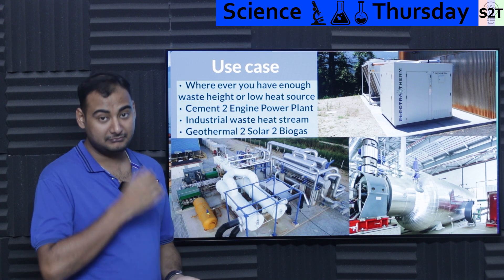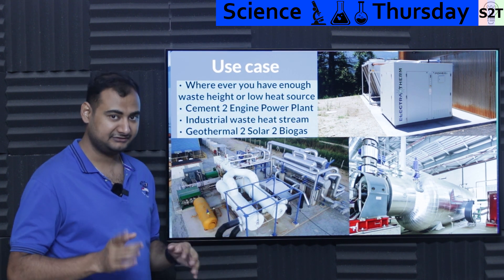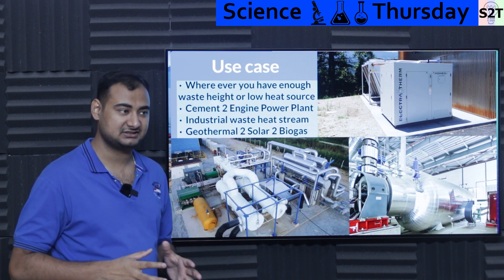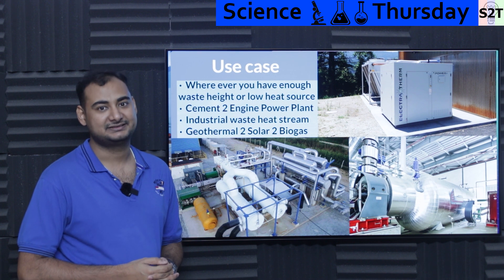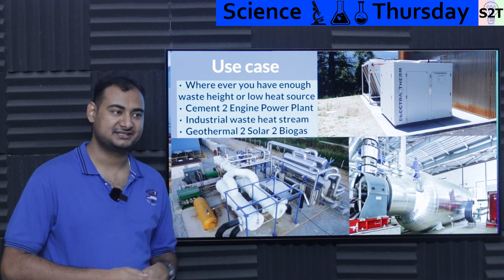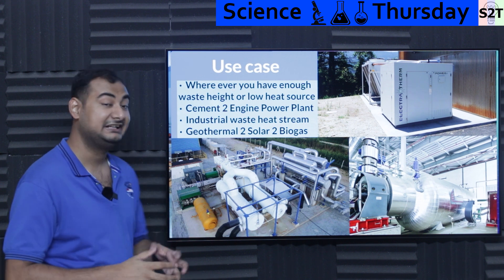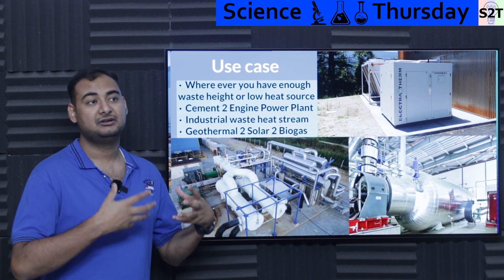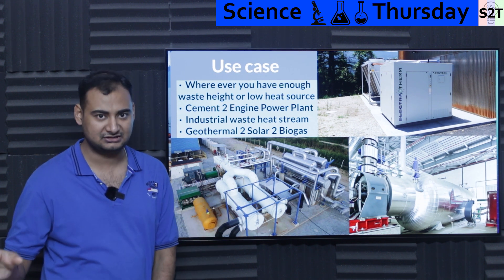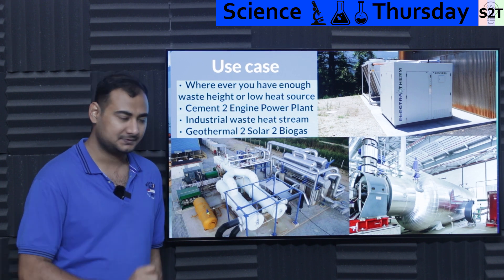The use cases are many, but ORC is generally used where you have enough waste heat. If your waste heat is only one or two kilowatts, you'll get maybe 100 watts out — it doesn't make sense to invest that much money for so little. You need at least a few megawatts of waste heat potential to extract a few useful kilowatts and make it financially viable, provided the generator design is done properly.